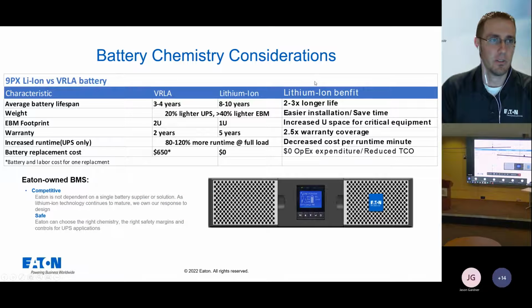Very similar when looking at our double conversion 9PX. Again we have 8 to 10 years, and what's unique with the 9PX is we offer extended battery modules, so a lighter UPS with lighter extended battery modules. What about footprints? We were looking at some of those IDF closets earlier, and there's not a lot of room in there sometimes. Sometimes it's just one little rack, but maybe you need some extra runtime. You go with a 2U base UPS and a 1U extended battery module, good to go. You get longer runtime at full load, and again, think about the battery replacement cost over a 10-year period.